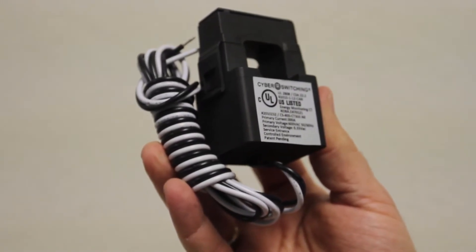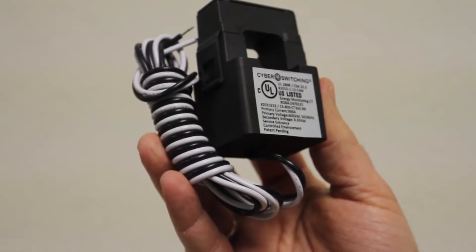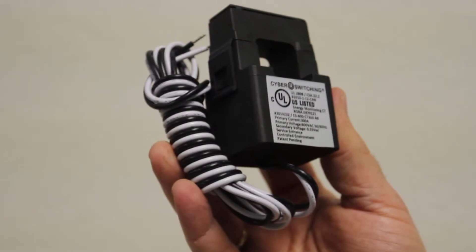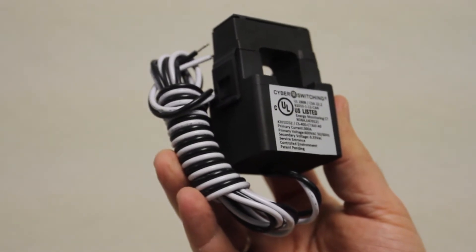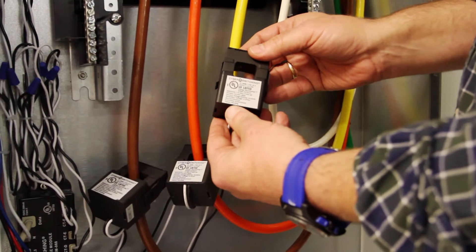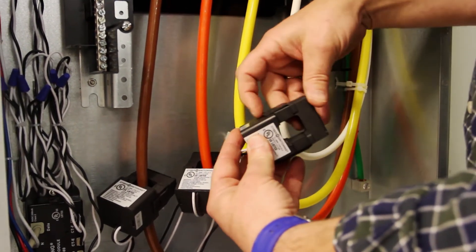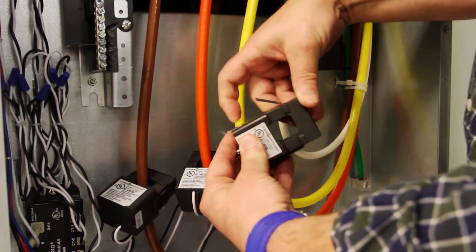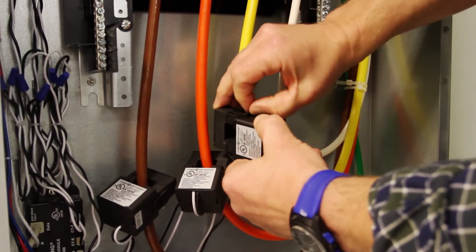The system starts with CyberSwitching's line of split-core current transformers. Coils are available in 50-amp, 100-amp, 300-amp, and 600-amp versions. These coils are UL2808 approved for field installation. With a convenient split-core design, the coil can be directly installed without having to detach from the primary line.